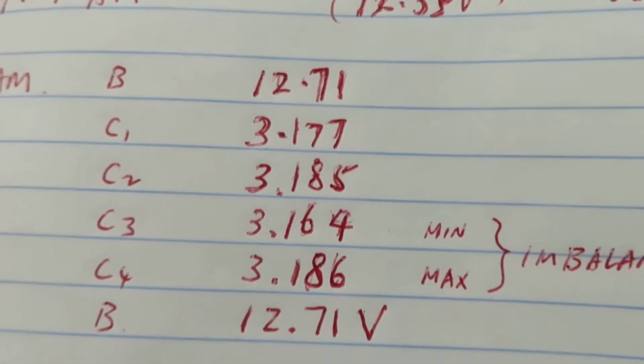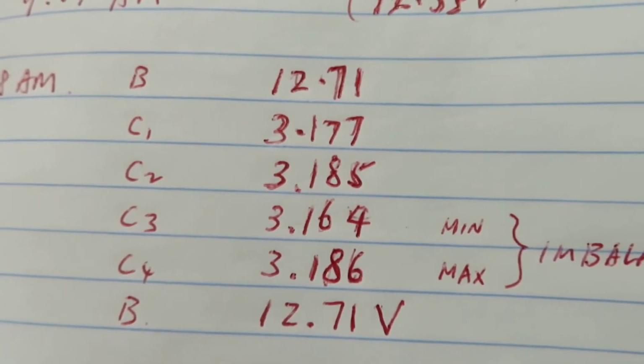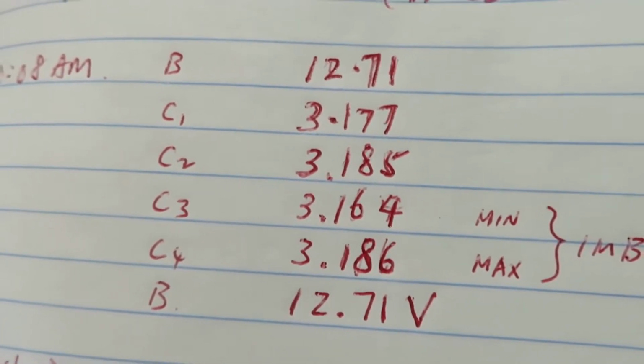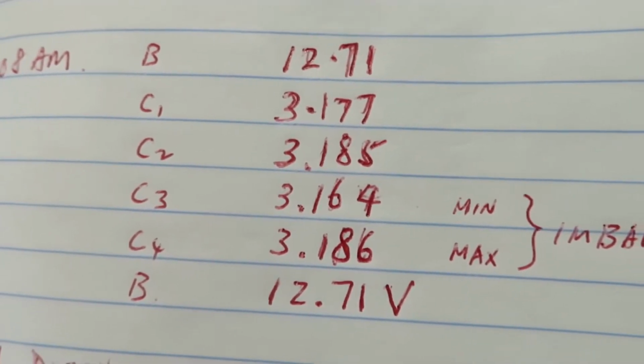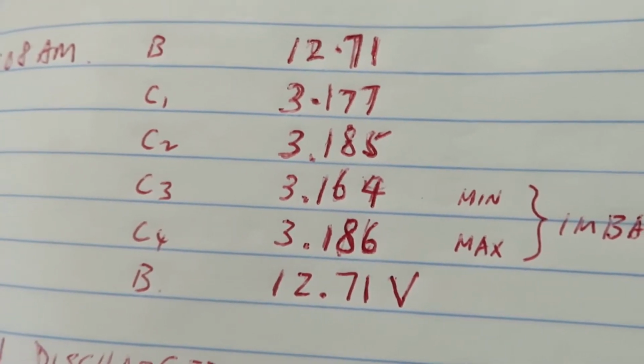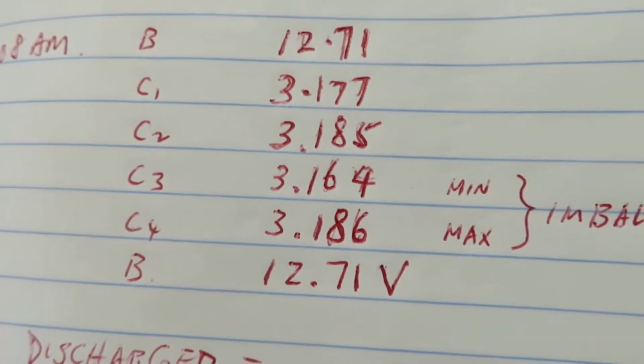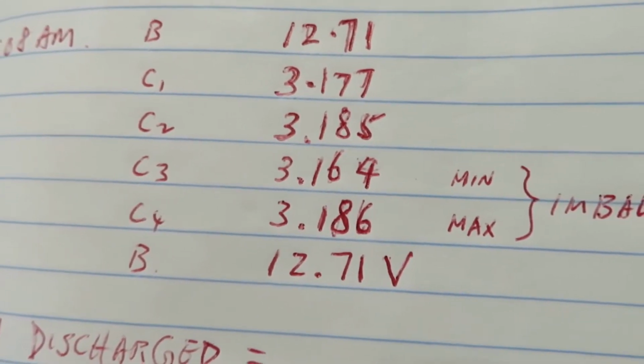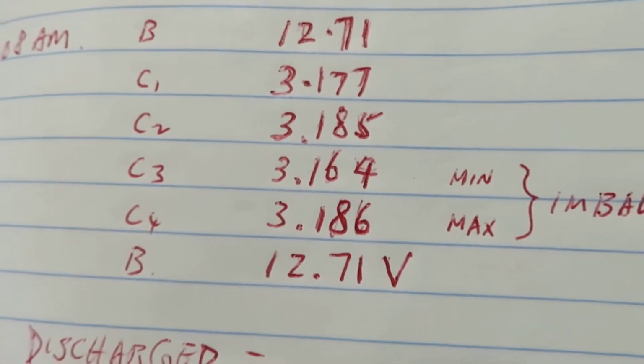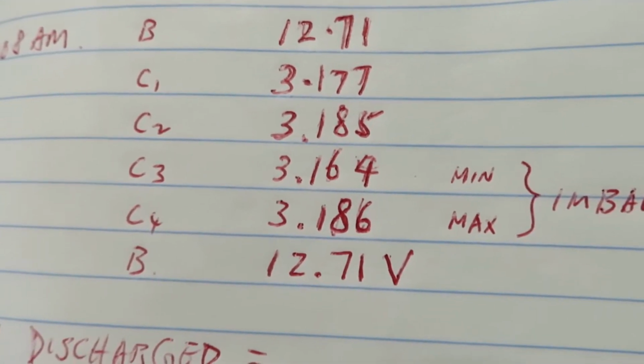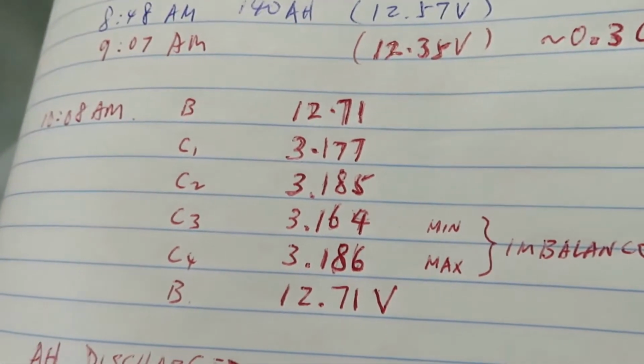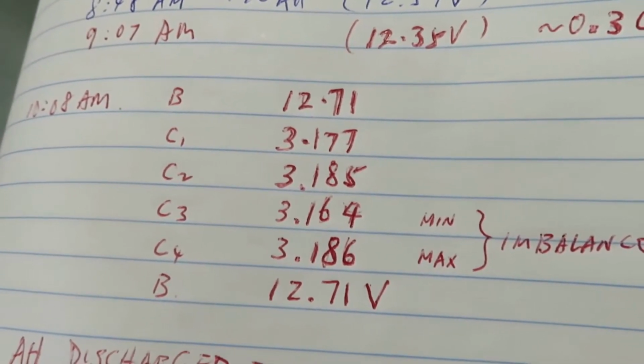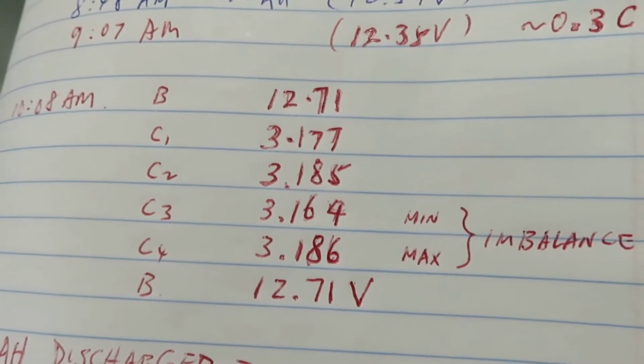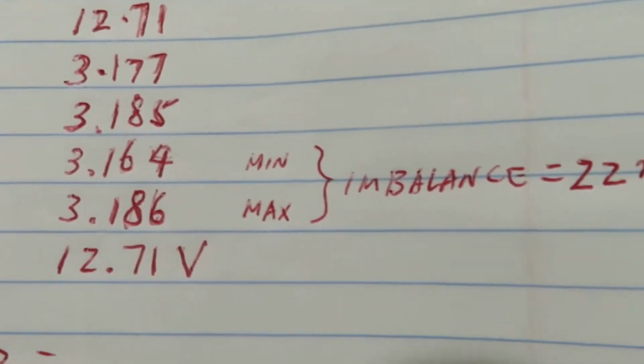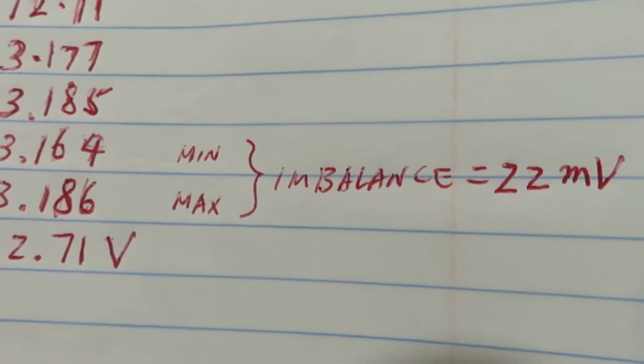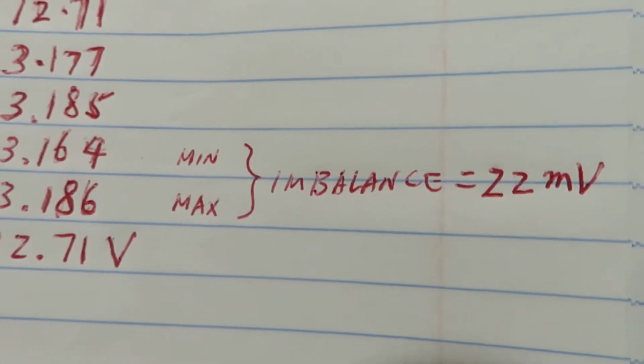And I measured the individual cell voltages from cell 1 to cell 4: 3.177, 3.185, 3.164, 3.186. So that all adds up to, again, 12.71. So the battery responds back quite a bit. And the cell imbalance is 22 millivolt.